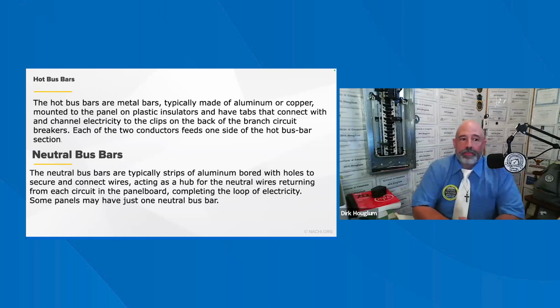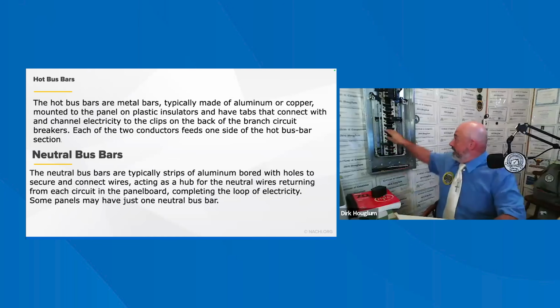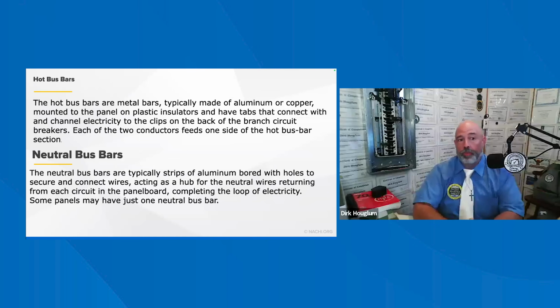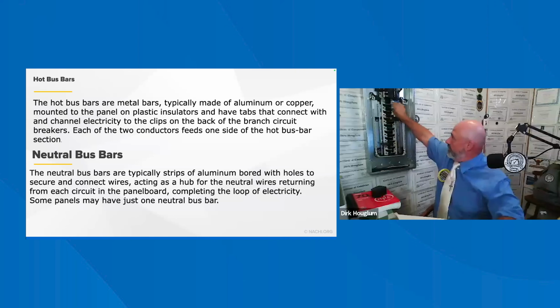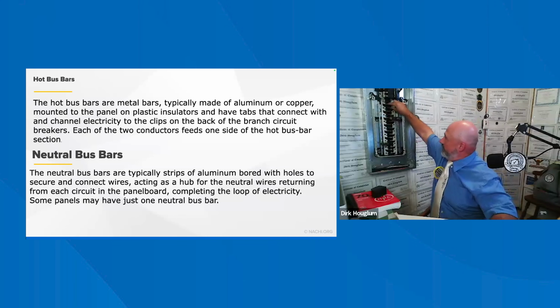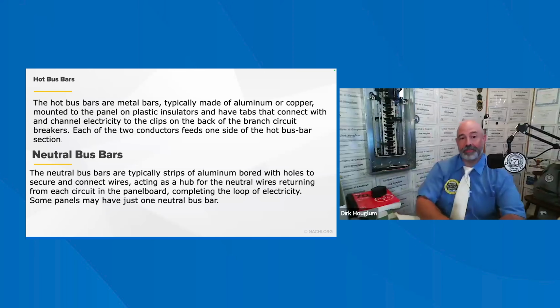Okay. The hot bus bars are the metal bars, that would be this stuff right here. Okay, don't touch this. If you touch that, you're dead, just FYI. They are mounted to plastic insulators behind there, with the channel electricity clips on the back for the branch circuit breakers. Each of the 2 conductors feeds one side of the hot bar in each section. That's why this one comes this way, this one comes this way, and that's why it clamps in here. It connects both of these together, 120 plus 120. Can't do math right now because we're getting to the end of this. So that makes it 240. Sorry. Okay, the neutral bus bars are typically strips of aluminum with bored holes to secure and connect the wires, acting as the hub.